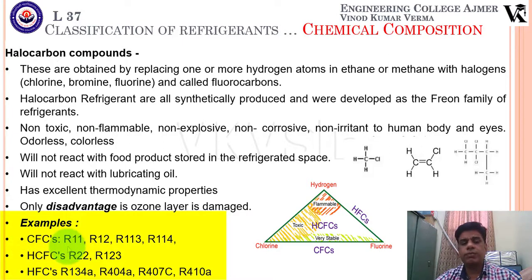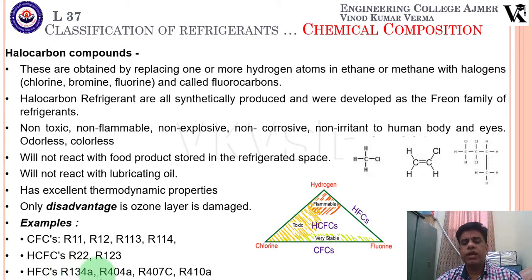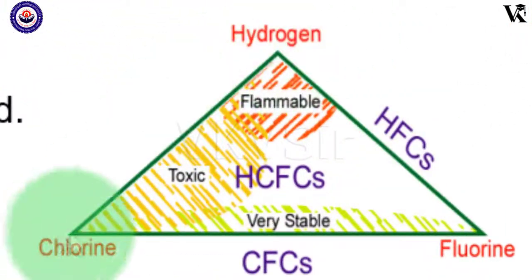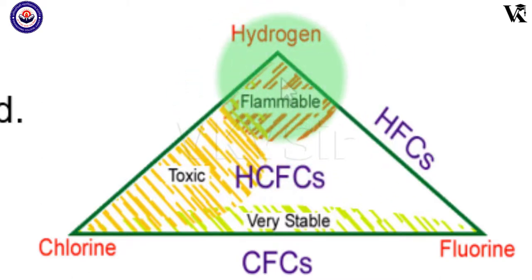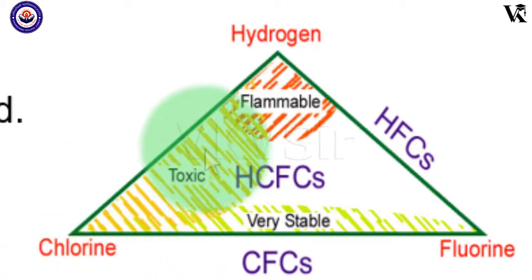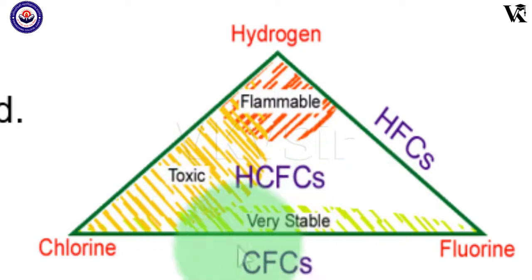Within halocarbons, there are subcategories. CFCs (chlorofluorocarbons) include R11, R12, R113, R114. HCFCs include R22 and R123. HFCs (hydrofluorocarbons) include R134A, R404A, R407C, and R410A. R134A is widely used in current scenarios. As we increase hydrogen content, flammability increases; as we increase chlorine content, toxicity increases. CFCs are very stable, which is why they were preferred earlier.